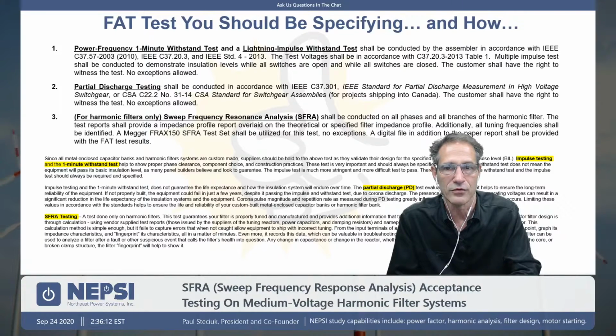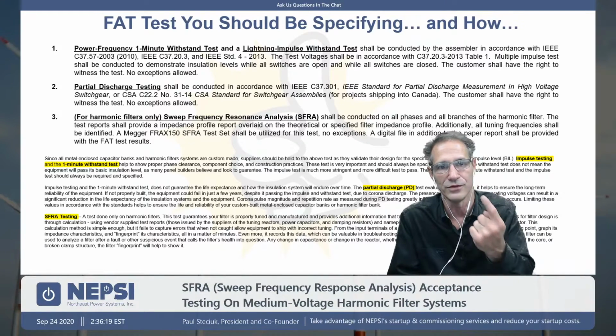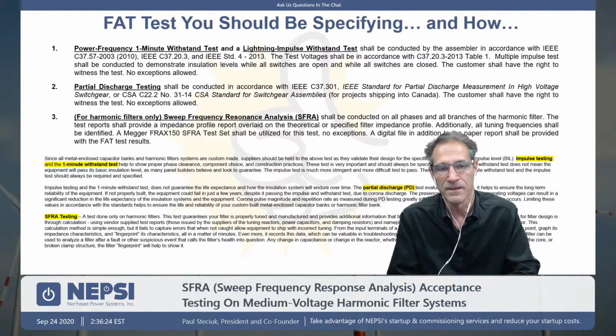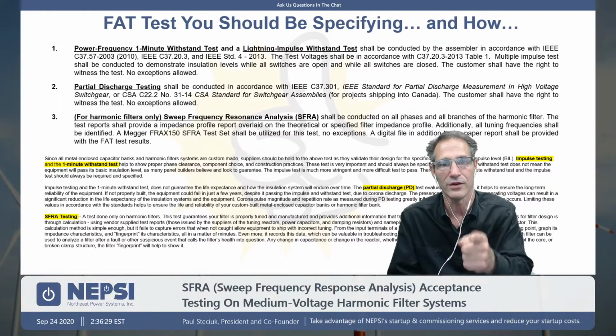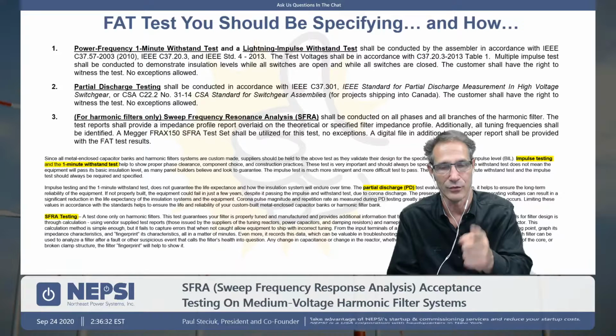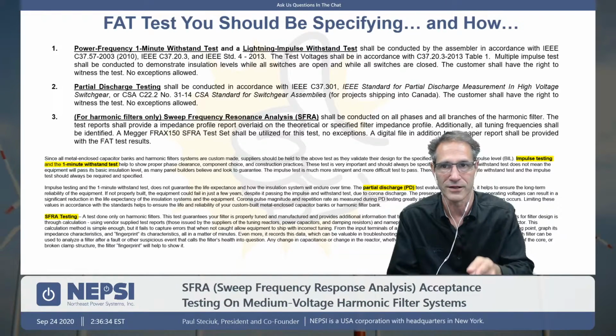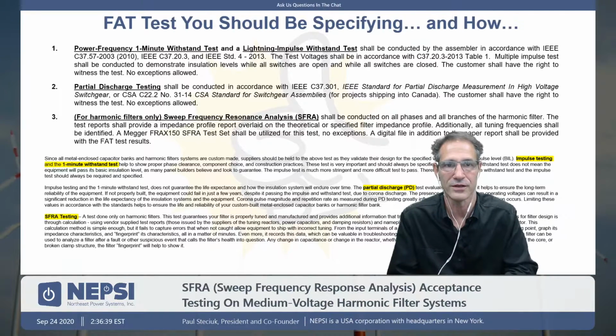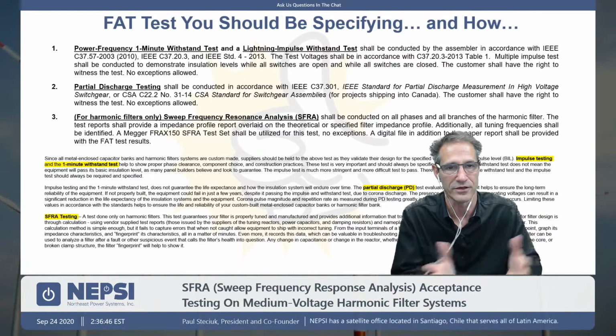Remember, metal-enclosed harmonic filters and capacitor banks are all custom in nature. And just like switchgear, when it's the first time you build it, you type test. Why? Because you want to make sure the design is good. If the filter bank or capacitor bank is being built for the first time, the only way to know you're getting what you asked for and that it works is that you did the proper tests. Impulse testing by far is important. We can't tell you how many times we impulse test our equipment and we find issues. The bolt is passed through too far, our phase clearance has been broken.